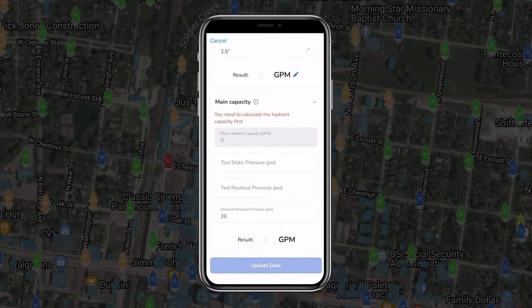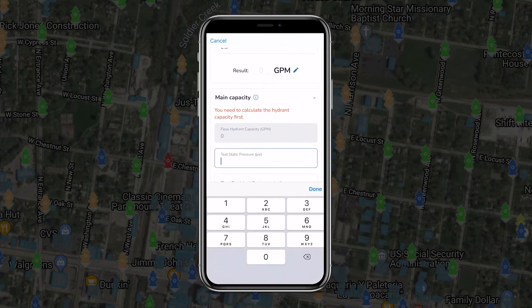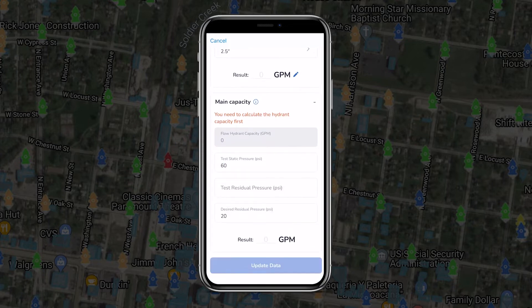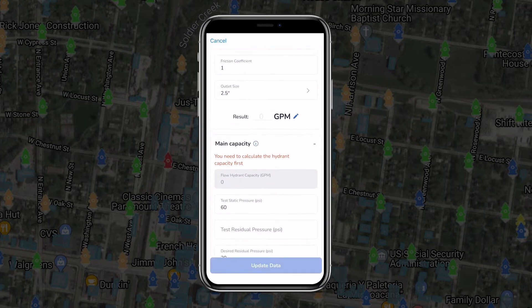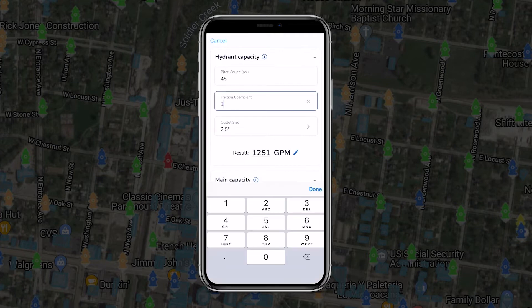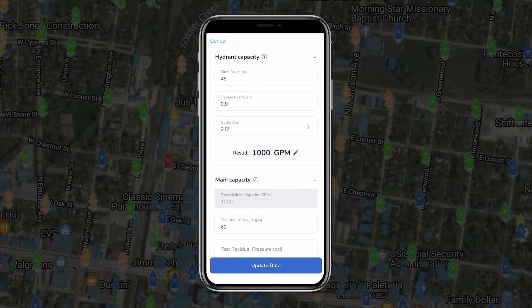They'll then close the cap gauge valve and take the static pressure reading. Once the static pressure reading has been recorded, another team member at the flow hydrant will measure and record the friction coefficient and the outlet size of the flow hydrant, and attach their pitot gauge for measuring pressure.